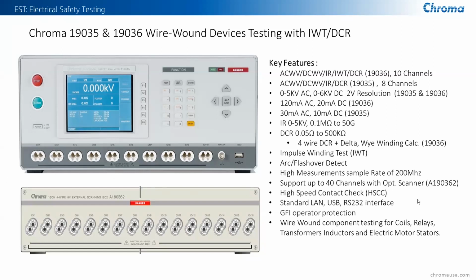This one again has a very high measurement sample rate, gets all the way up to as high as 200 megahertz bandwidth. And with this one, you can go with an external scanner box up to 40 channels. And again, it has a standard Ethernet, USB, and RS-232 interface, and it will also protect the operator with GFI. It gives you the ability to do higher currents, up to 120 milliamps of AC, 20 milliamps DC with the 19036. We also offer a 19035 version of it that doesn't include impulse winding test.